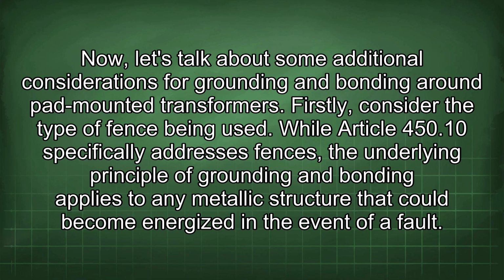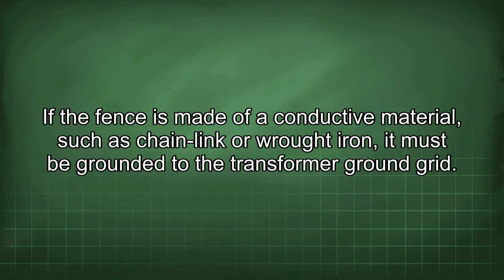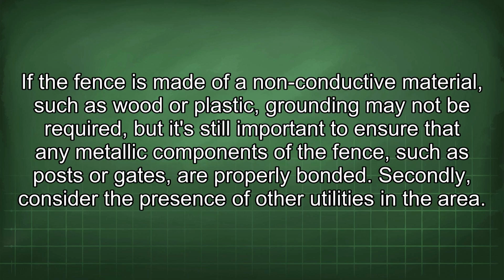Now let's talk about some additional considerations for grounding and bonding around pad-mounted transformers. Firstly, consider the type of fence being used. While Article 450.10 specifically addresses fences, the underlying principle of grounding and bonding applies to any metallic structure that could become energized in the event of a fault. If the fence is made of a conductive material, such as chain link or wrought iron, it must be grounded to the transformer ground grid. If the fence is made of a non-conductive material, such as wood or plastic, grounding may not be required, but it's still important to ensure that any metallic components of the fence, such as posts or gates, are properly bonded.